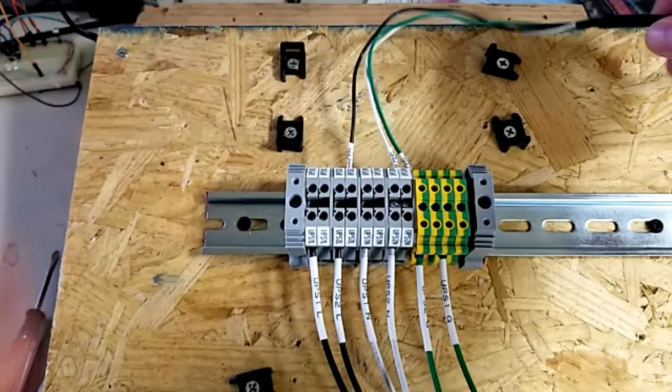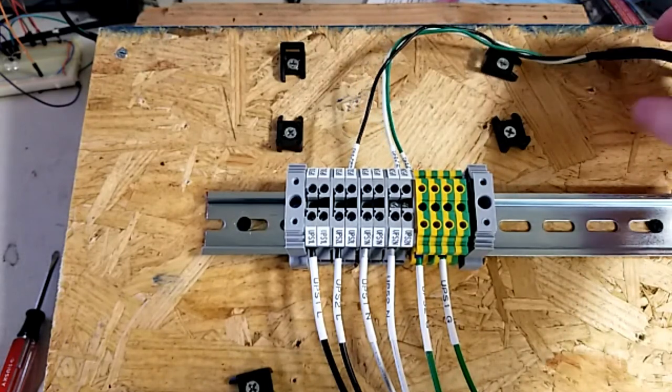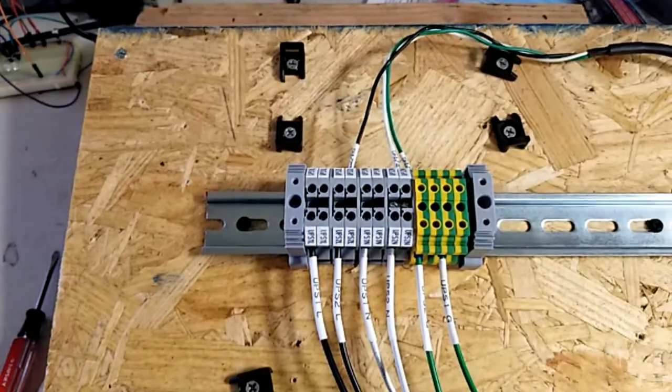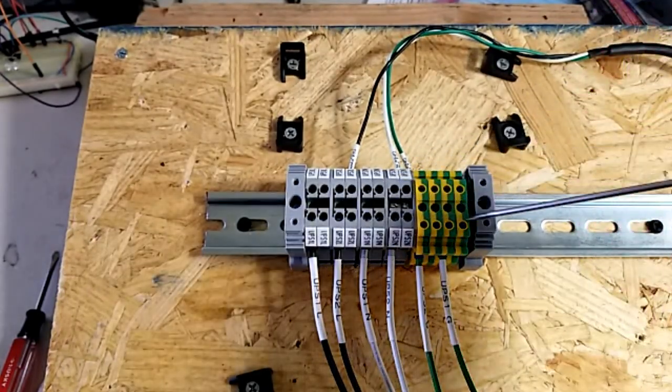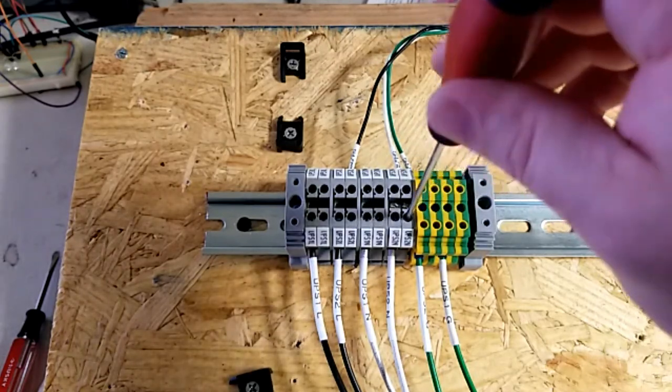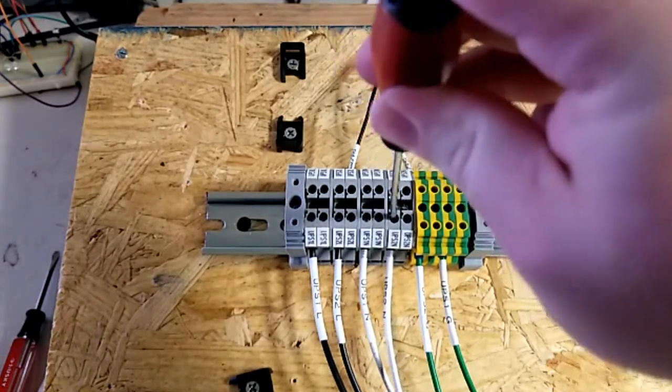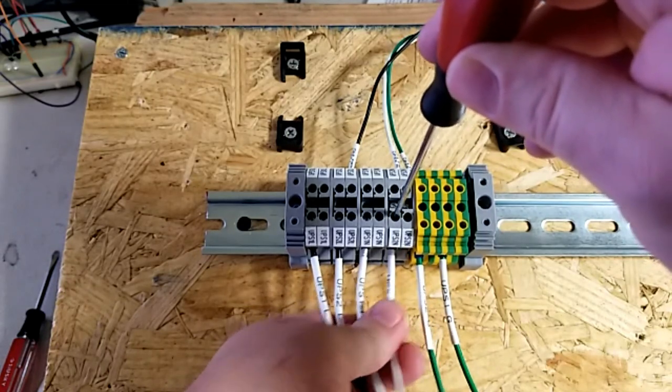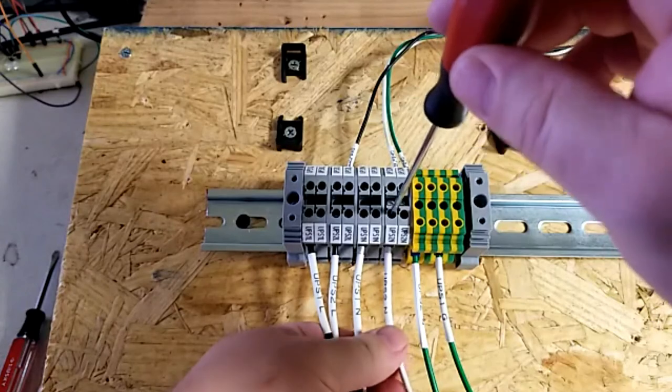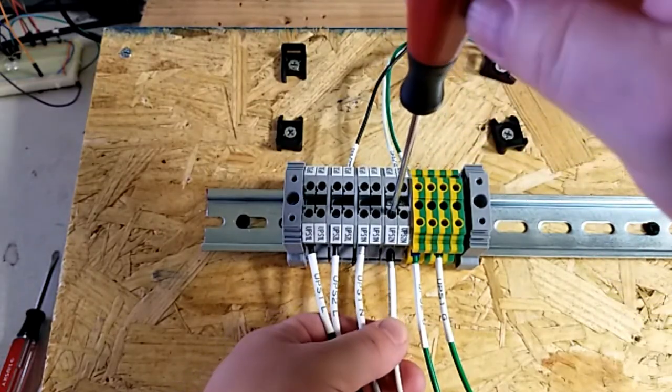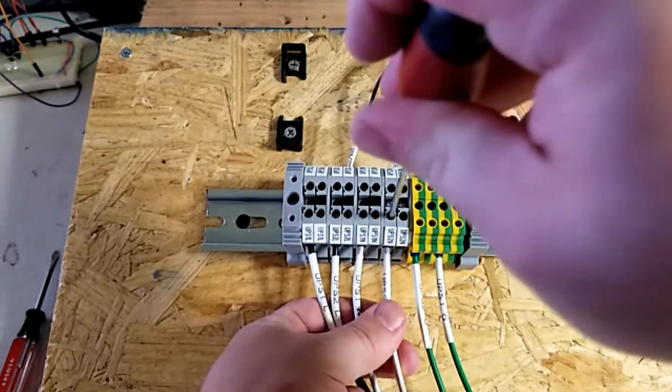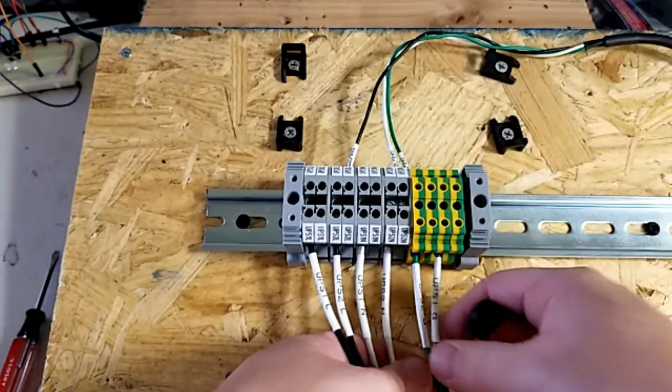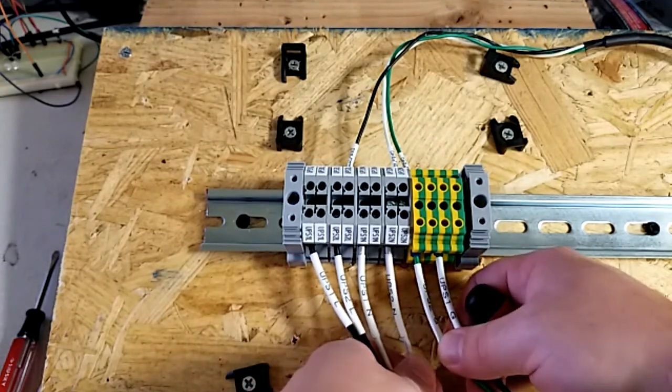From there, then you can go ahead and route this cable back over to PC4. Zip-tie it back in place, make sure everything's nice and clean and routed. Go ahead and go through all of these terminals, any terminal that has a wire connected to it, and make sure that the screw is snug down tight, the wire is fully seated in the connector, and give it a tug test. Make sure that it's tight. If any of them look like they're not fully seated, just go ahead and loosen up a little bit and get it pushed all the way back in, and then tighten it back down. Again, you want to make sure that all your wires are tight, fully seated, and tight into the screw terminals.